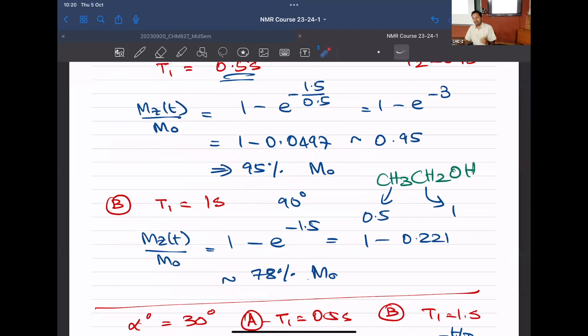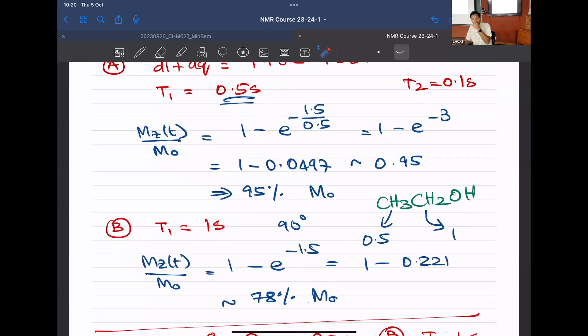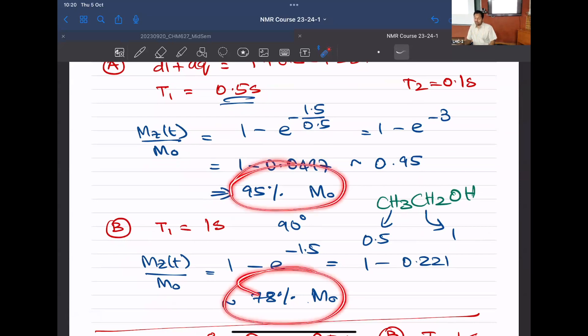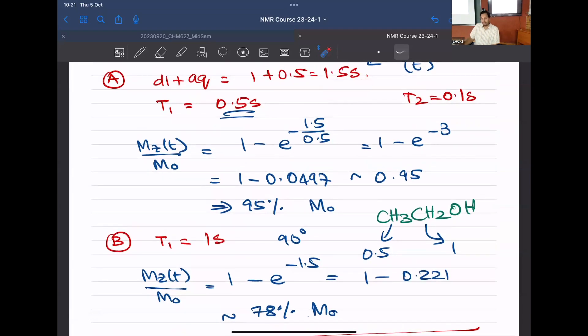After perturbation, you're not allowing all spins to return to equilibrium — you can't wait that long. So you cut the recycle time and get the spectrum faster. The consequence is non-uniform recovery. Carbon spectra are seldom integrated to count carbons because T1 times are vastly different across carbons. A 30-degree pulse experiment helps but won't recover everything completely. For systems with very long T1 (e.g., 5 seconds) and D1 + AQ still at 1.5 s, the disparity becomes much worse — especially for biomolecules.